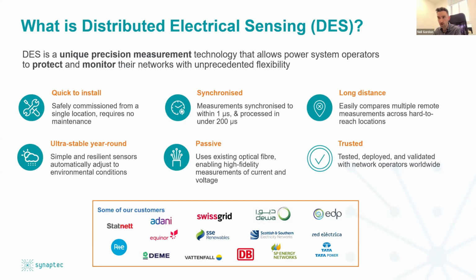The sensors are passive, so they don't require digital telecoms or power supplies or GPS access at the measurement location. It operates over extremely long distances, further as standard than any other power networks monitoring approach. As I've said, it's passive and it's stable year round under different weather conditions. It's inherently cyber secure because of the methods that we use. And most importantly of all, it's tried and tested by operators in the field and has been for several years. It's been deployed for several years now with operators in the UK, in Europe, in the Gulf states, in India, and across terrestrial T&D applications as well as offshore wind.